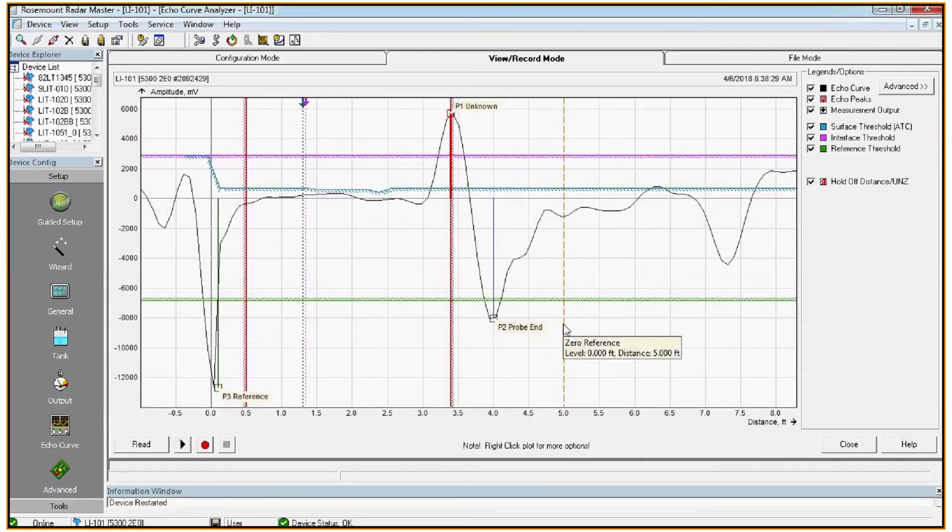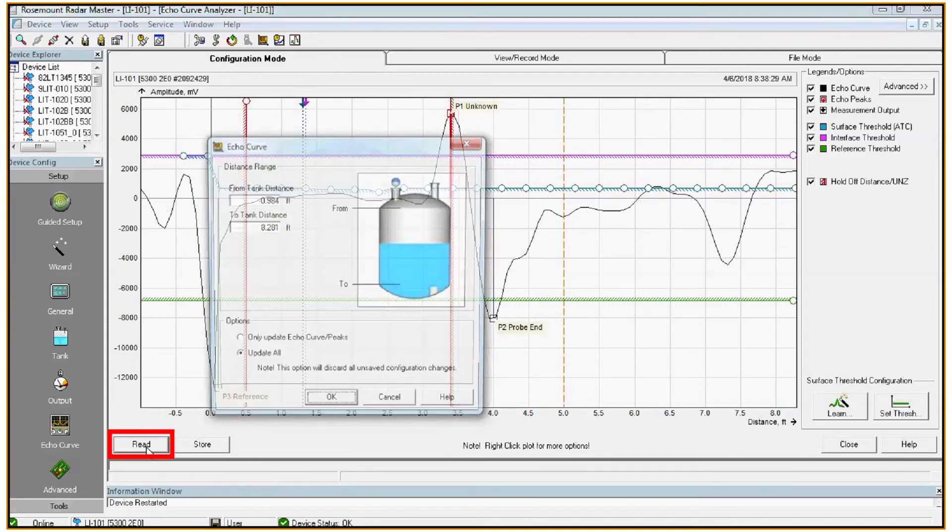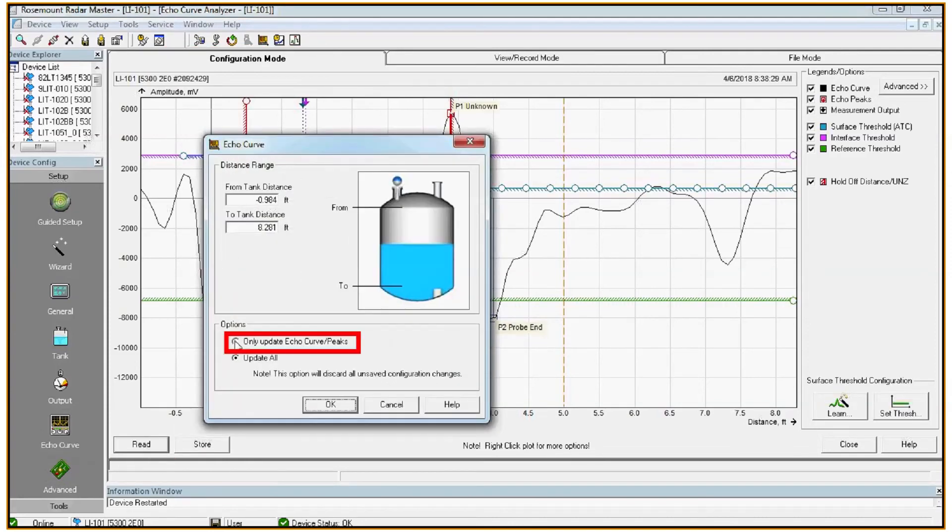Now that we saved an echo curve with the tank empty, it's a good idea to introduce product into the tank and load and save another echo curve. Go to configuration mode. Click read. Click only update echo curve slash peaks. This will make the echo curve load faster and hit OK.